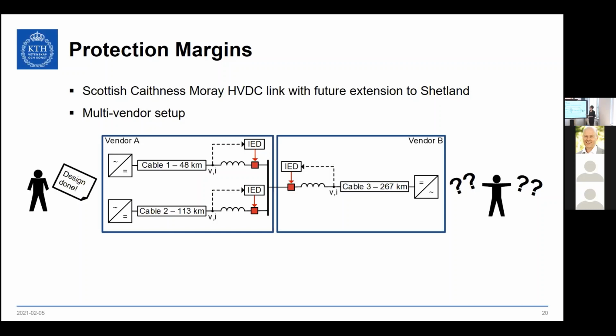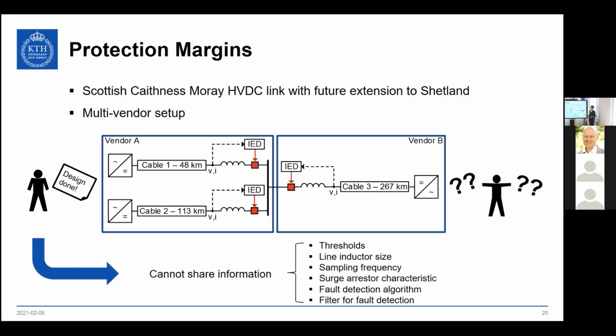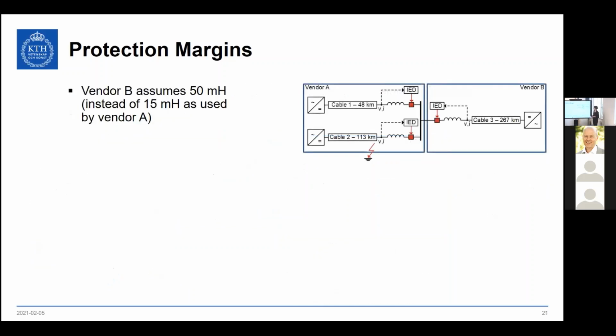The second vendor comes in, and now the question is how to design the protection. What I did here is I investigated what happens if vendor A cannot share a certain piece of information, for example, due to intellectual property rights. I investigated a few different ones, and here I just want to show you one example. What happens if vendor B has to design the HVDC grid protection and does not know what vendor A installed as line inductor size here? So the assumption is, in detail, vendor B assumes 50 millihenries installed here, but in reality it's only 15 installed.